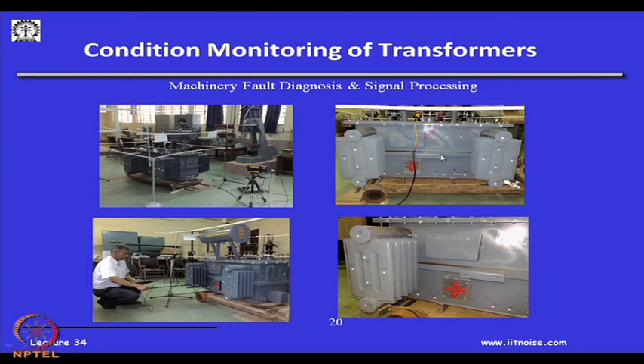But usually the condition monitoring of transformers is done by monitoring the condition of the oil. We discussed oil analysis. By monitoring the condition of the oil, whether it has retained its physical or chemical properties, we can know, periodically by taking samples of the transformer oil, whether it has got contaminated with moisture, whether it is time to change the oil etcetera. That is how these transformers are taken care of.